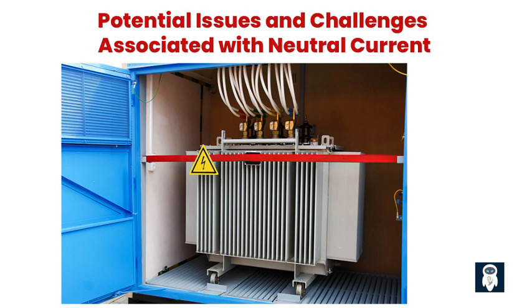Potential issues and challenges associated with neutral current: 1. Overloading and overheating due to neutral current. Neutral current can cause serious problems if left unchecked. One major issue is overloading and overheating of the transformer. When the neutral current exceeds the rated capacity of the transformer, it can lead to excessive heating and potential damage, resulting in costly repairs or even the need for a complete replacement.